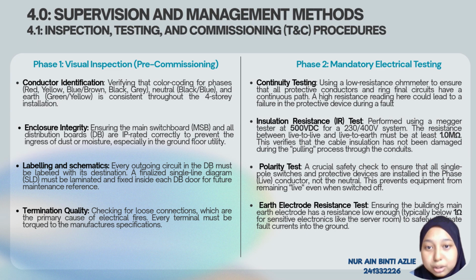Next is enclosure integrity, ensuring the main switchboard (MSB) and all distribution boards (DB) are IP rated correctly to prevent the ingress of dust or moisture, especially in the ground floor utility room. Next is labeling and schematics. Every outgoing circuit in the DB must be labeled with its destination. For example, level 2 is server room aircon. A finalized single line diagram (SLD) must be laminated and fixed inside each DB door for future maintenance reference.